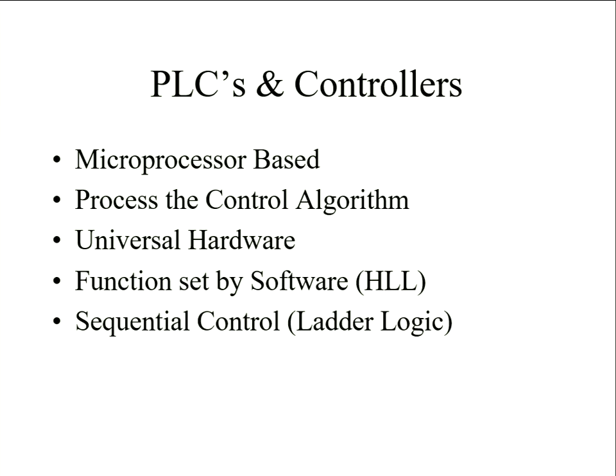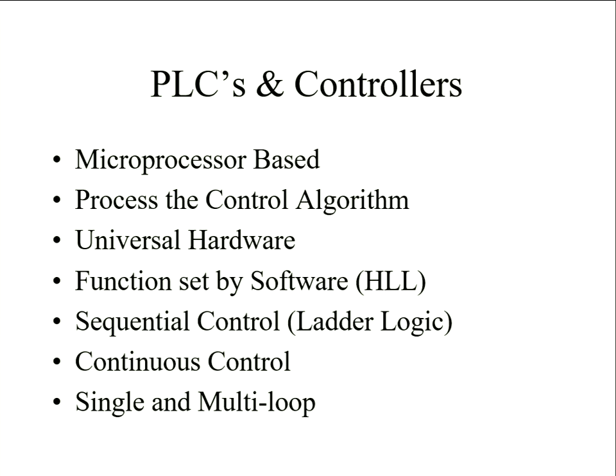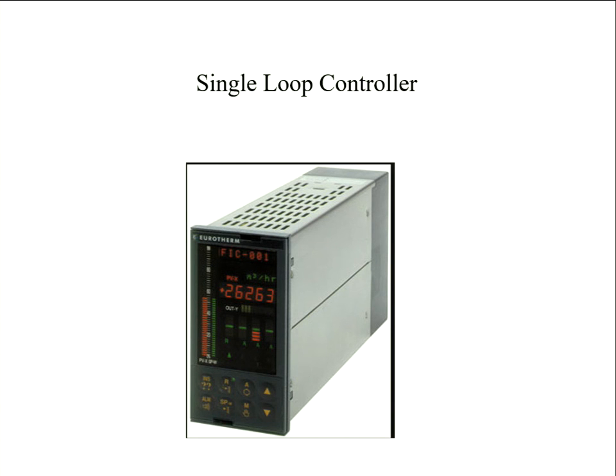Distributed control systems are typically within a single site. They have higher speed data links, so local area networks, and a lot of closed loop control. Now that's not what we tend to see in the UK gas industry. What it is, is lots of little process plants. This is probably more common. So if I went over the fence onto the producer's side, you'd see this sort of stuff. And sitting within it might be multiple controllers, programmable logic controllers. Probably the nearest I've seen on the national grid side of things are the compressor stations. So you've got multiple compressor units, and each compressor unit maybe has suction pressure control, discharge pressure control, flow control, discharge temperature control, along with a whole bunch of safety things that say switch off if temperature gets too high, exhaust cone temperatures and so on.